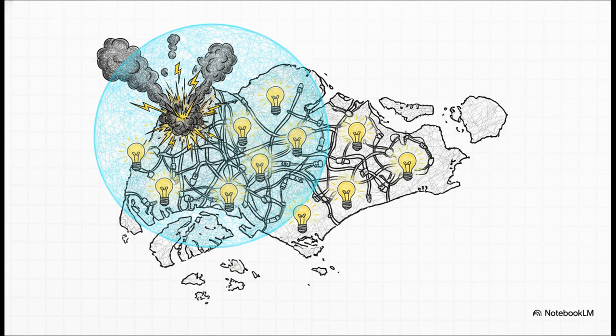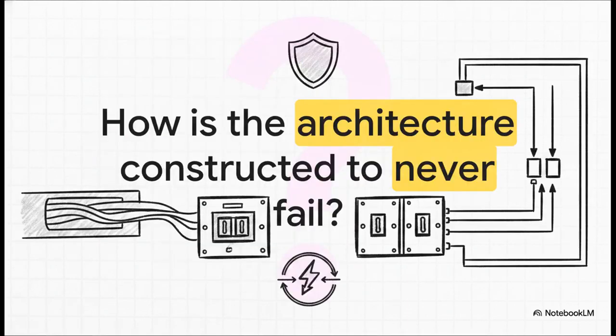On a small, densely interconnected island that has absolutely no overland backup power to import in an emergency, the N-1 rule guarantees that one exploded transformer results in exactly 0 cascading failures, 0 system instability, 0 load shedding. The lights shouldn't even flicker for the end consumer. But here's the catch. Getting that level of reliability costs serious money and effort. It literally requires building extra, quote-unquote, wasted transmission capacity that the grid hopes to never actually use. It's purely physical insurance.